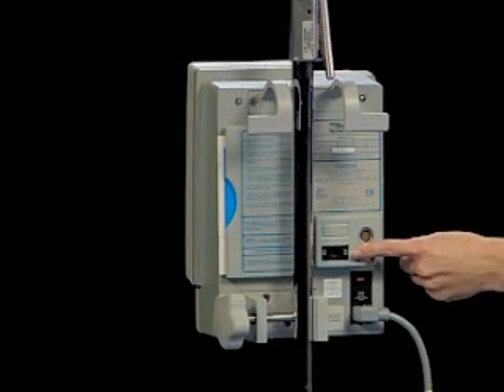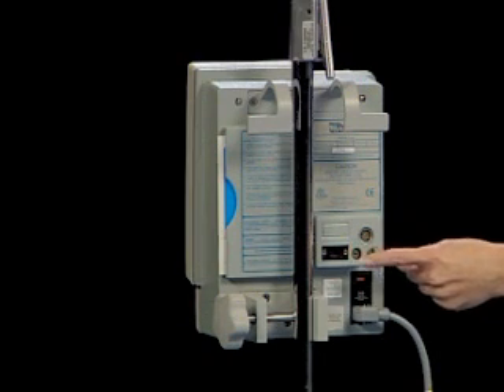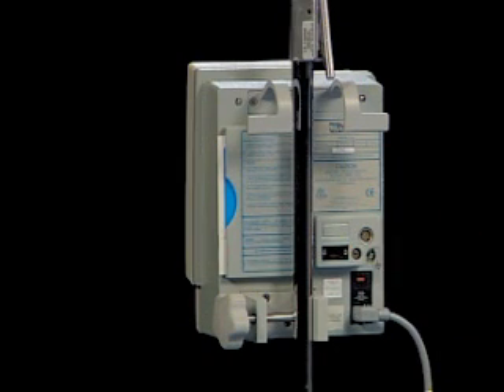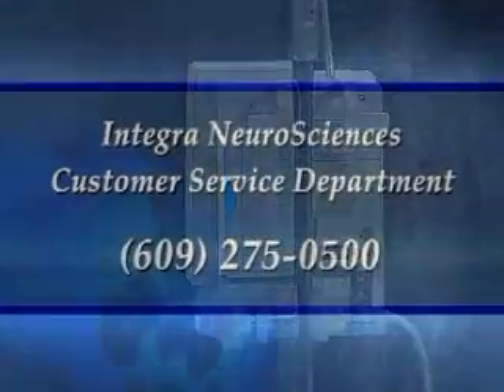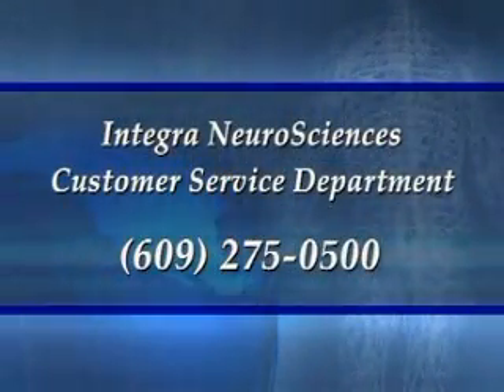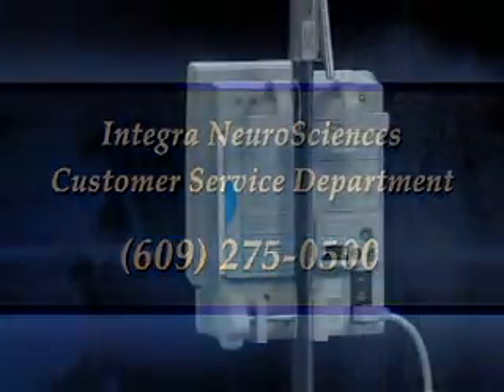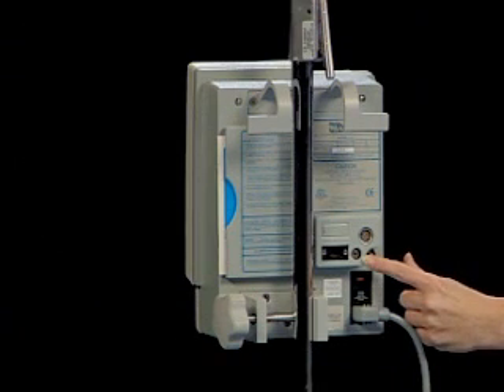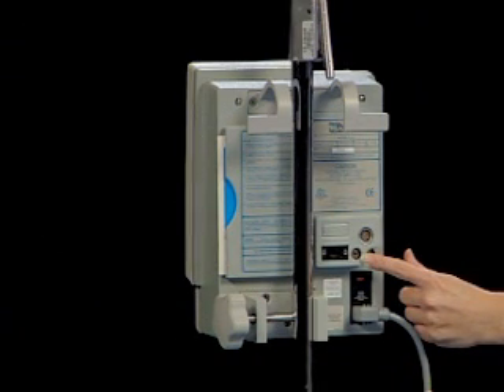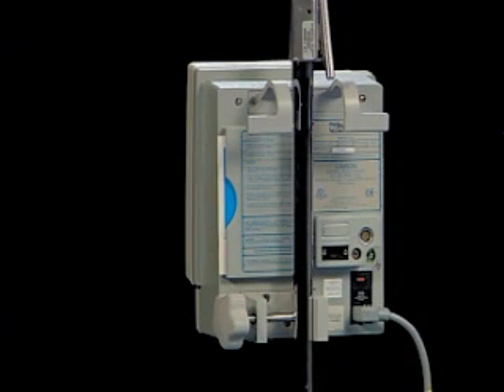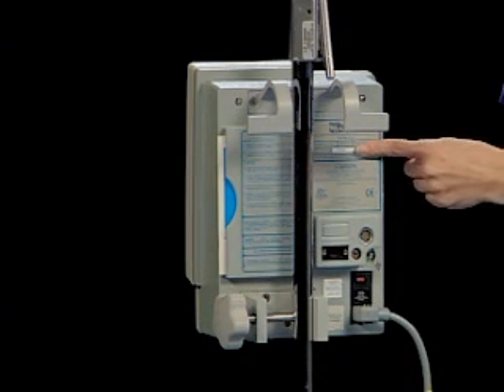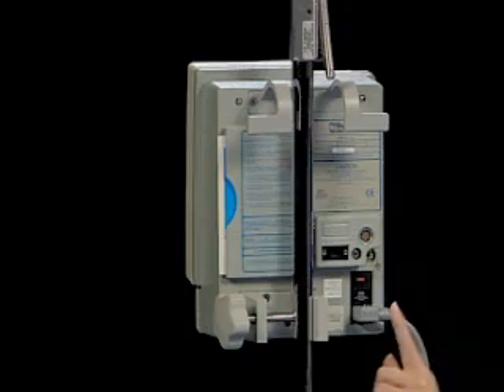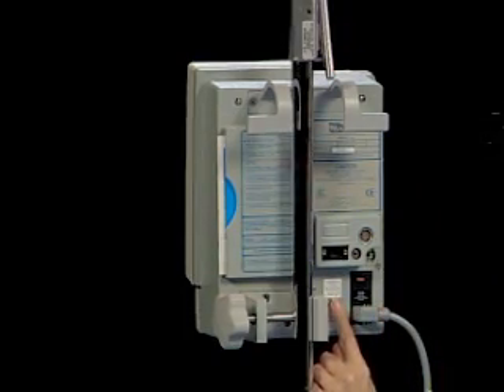The RS-232 serial port is used to connect the MPM to a personal computer for data acquisition needs. Optional software is available for trend analysis. Please call Integra Neurosciences customer service at 609-275-0500 for more information about this software package. The analog output connector can be used for data acquisition. Please note the location of the serial number and the date of next scheduled maintenance. Preventive maintenance and monitor calibration is required every 18 months.